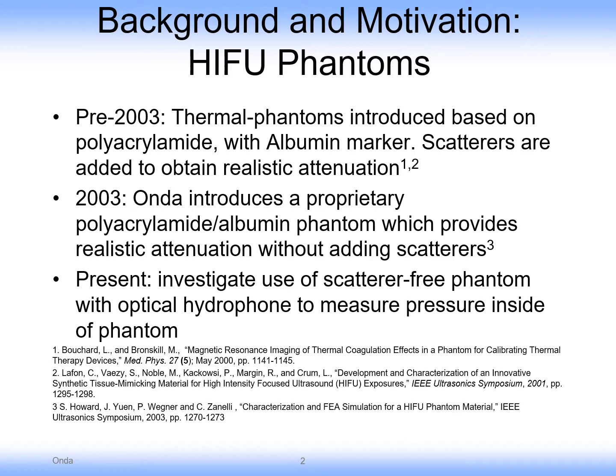Phantoms are obviously useful for HIFU, for dosimetry, as well as checking on the performance of HIFU equipment. Prior to 2003, thermal phantoms were introduced based on polyacrylamide as the phantom matrix, with albumin added as a marker inside of that matrix. The albumin, upon achieving a temperature, would denature and change optically, or its performance in magnetic resonance imaging equipment would change.